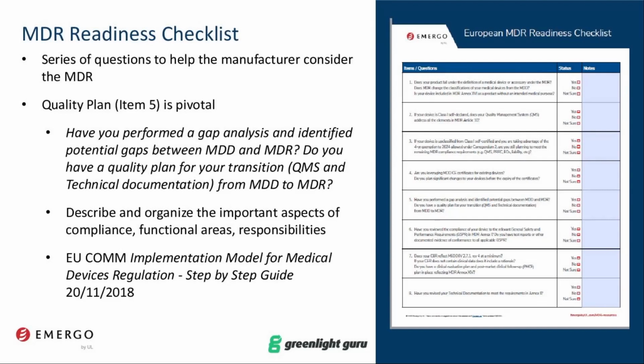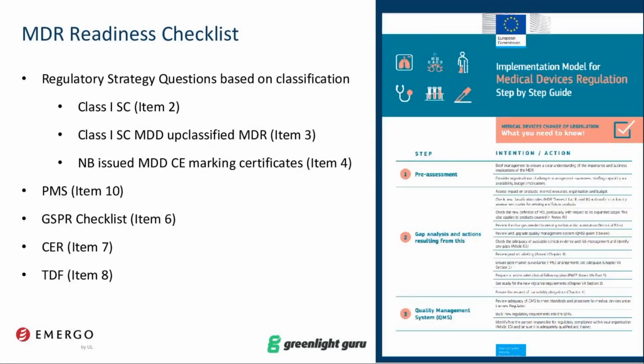Just to make a comment, the EU Commission has a good document that they released in 2018 titled Implementation Model for Medical Device Regulations. It's also a series of step-by-step questions to help guide a manufacturer through that process. As part of this readiness checklist, and you'll see an image on the right side of that EU Commission implementation model document, we should remind everyone that when the medical device regulation was drafted, many of the European medical device guidances, the MedDevs, were incorporated as legal text into the MDR. One thing a manufacturer should do is continue to monitor for guidance, because even with many MedDevs incorporated into the MDR, the Medical Device Coordination Group, which was established by Article 103 of the MDR, is also releasing guidance documents, as are other parts of the EU Commission.